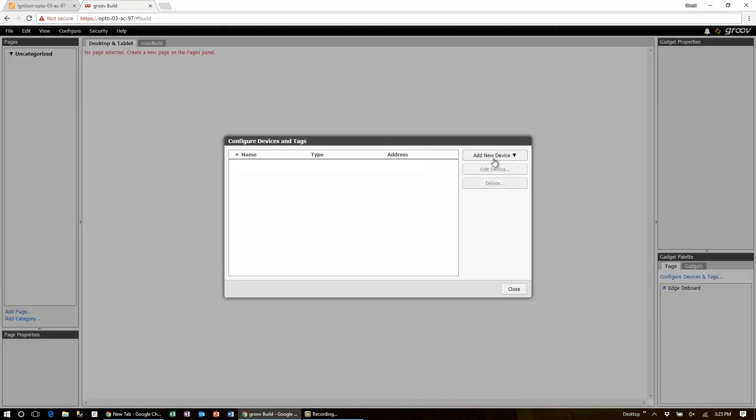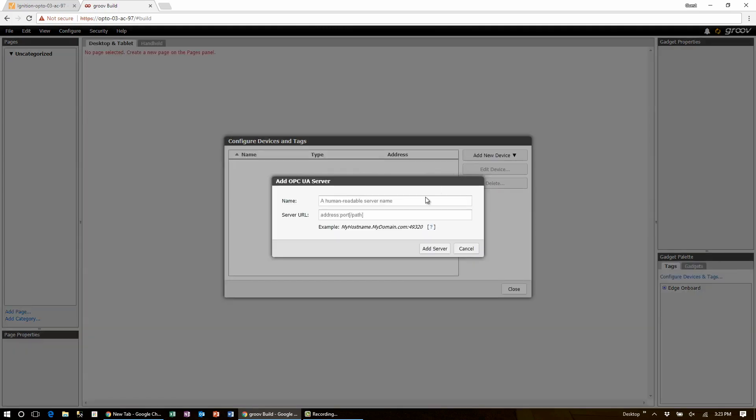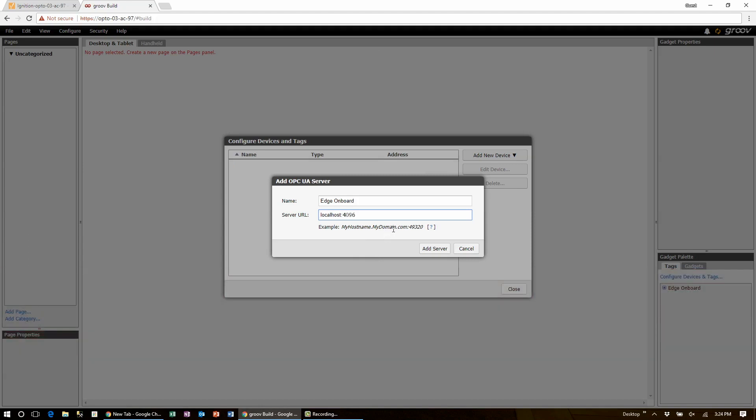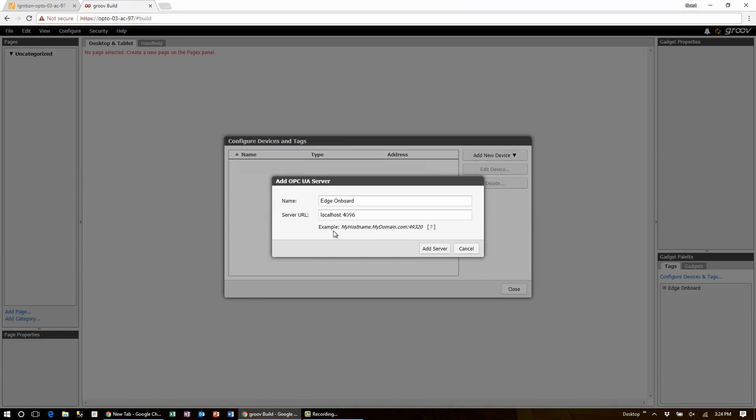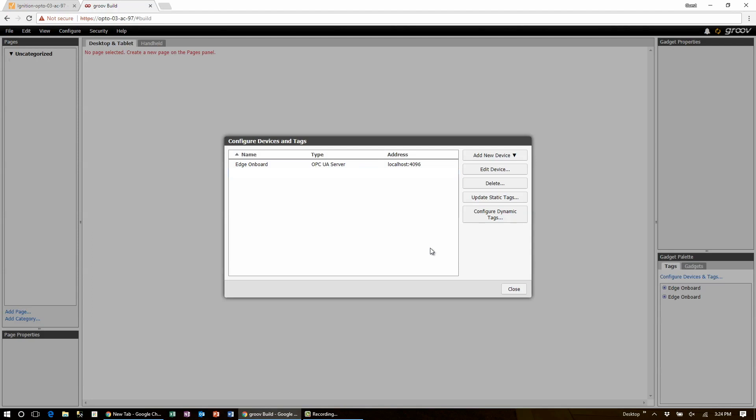Let's drop down the add device option and select OPC UA server. Let's give it a name and for the server URL it's important to use localhost colon 4096. If you forget the port number you can just click on the little question mark and it will provide a hint for each type of the OPC servers. Finish up by clicking add server.